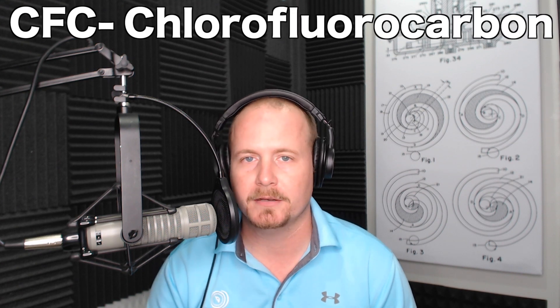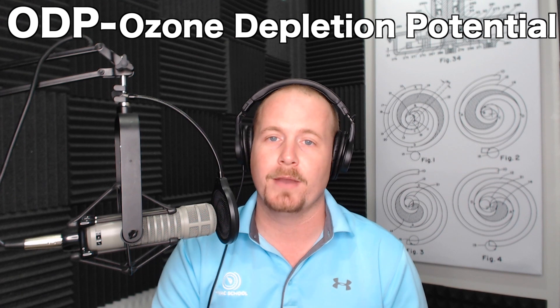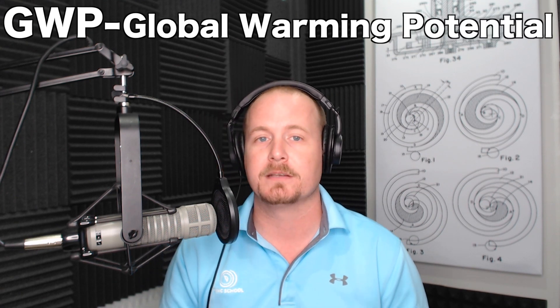Let's identify some acronyms. CFC stands for chlorine, fluorine, carbon. Chlorine is the part we worry about according to the EPA and the global community — it's the chlorine that gets up into the stratospheric ozone and damages it. That's the ODP, ozone depletion potential. Then you have GWP, global warming potential. Even some refrigerants like HFCs — hydrogen, fluorine, carbon — have no chlorine, but according to the international environmental community, they still have a high global warming potential. R11 and R12 are the old refrigerants traditionally called Freon with high ODP. R22 is an HCFC — hydrogen, chlorine, fluorine, carbon — which still had chlorine in it, so it still had some ozone depletion. That's what's been used as a refrigerant until now.